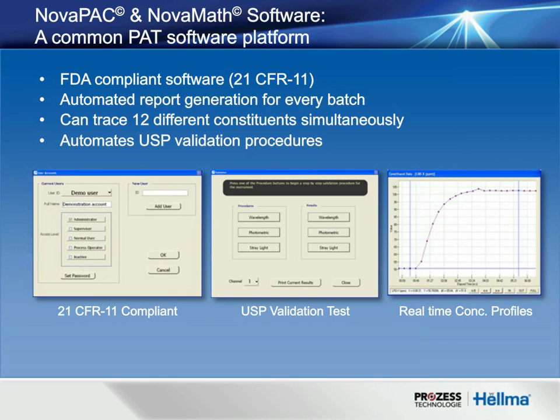Sure, thanks, Evan. So before talking about that, I also wanted to mention that we had talked about it on a previous slide about how this actually works. But in addition to the hardware component provided, the analyzer that Prozess develops, the sample interfaces that Hellma develops, Prozess also has control and chemometric software that has been around for now about a dozen years. With that is also critical to this aspect. So not only all the necessary compliances, but it enables the real-time use of these models. As I said, typically up to 12 different constituents that can be tracked simultaneously, and this can be in millisecond time frames. And also the controls to automate the internal calibration procedures and validation procedures for USP.